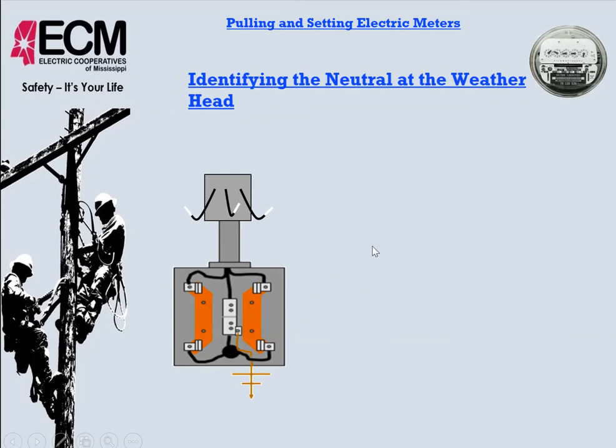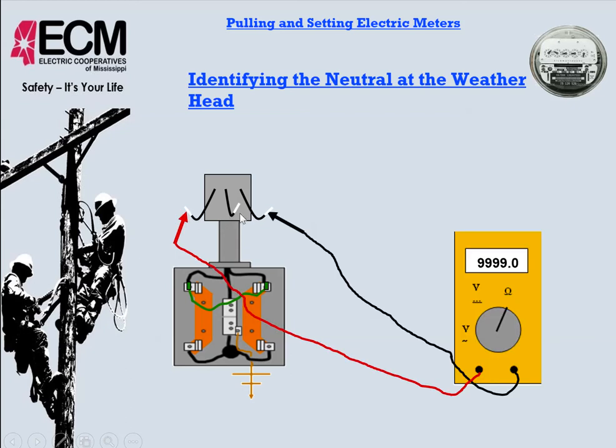And then the next thing that we want to do in identifying our neutral is, there are a couple of different ways. One of the first ways we're going to look at is you take a piece of wire and connect your 2 line sides together, okay? Once we connect them together, there's continuity between those two. So then we're going to go up the ladder with our multimeter set to ohms, and we're going to strip all 3 of them out, and we're going to touch it to 2 of them. Now, if we have our line sides connected together, which would have continuity between those two, and we touch 2 of our wires, and it shows an infinite amount of resistance, which one is our neutral?